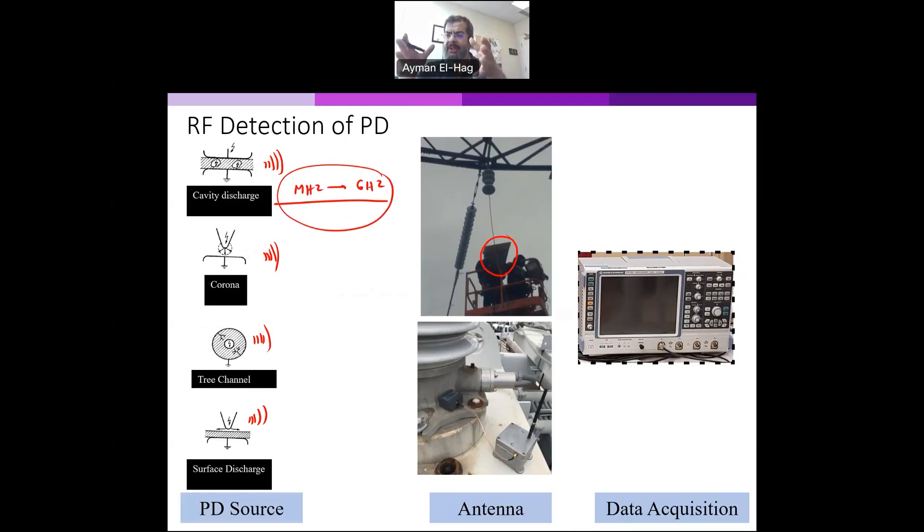For example, you cannot use an oscilloscope with a bandwidth of one megahertz or less than that, or a bit more than that. You will not detect most of the energy of the partial discharge. So that matching between the source of the partial discharge, the sensor which here is the antenna, and the data acquisition system is extremely important.